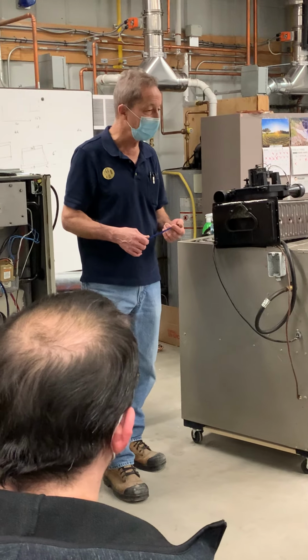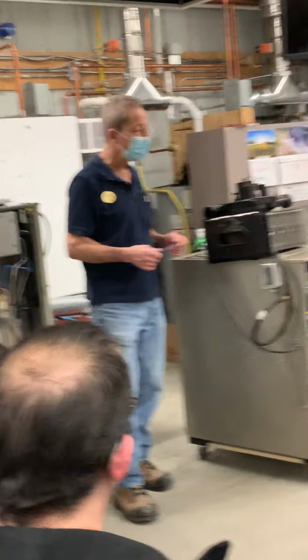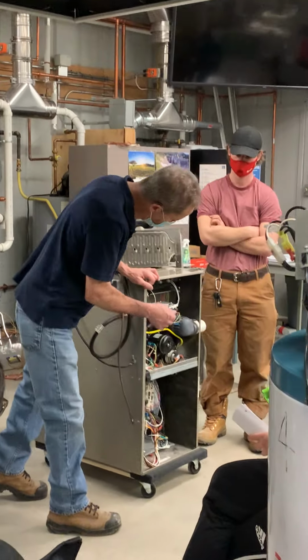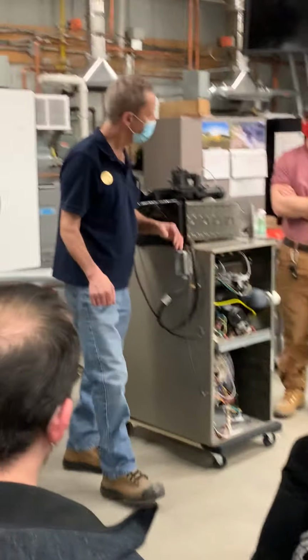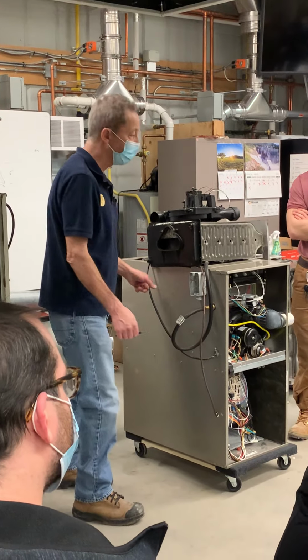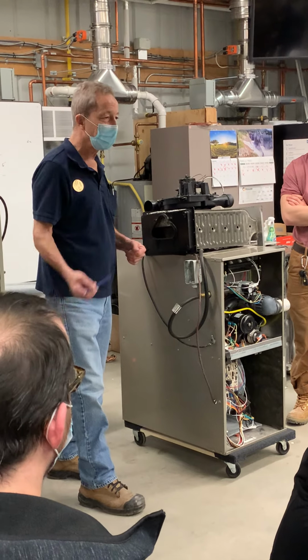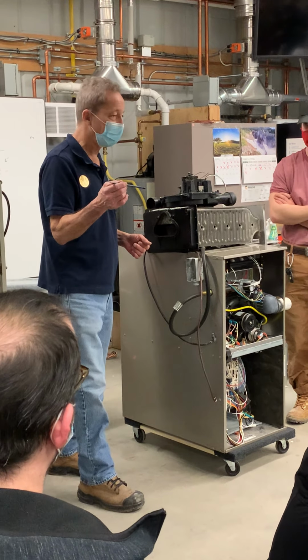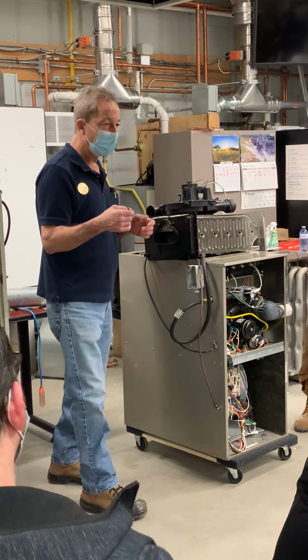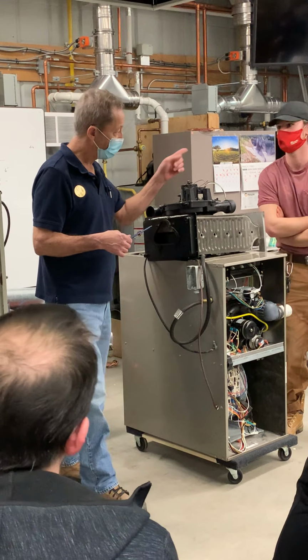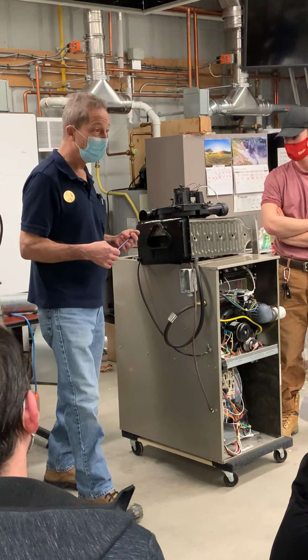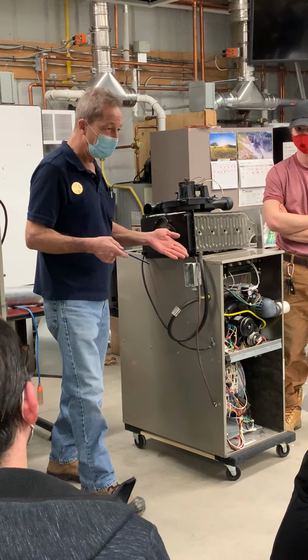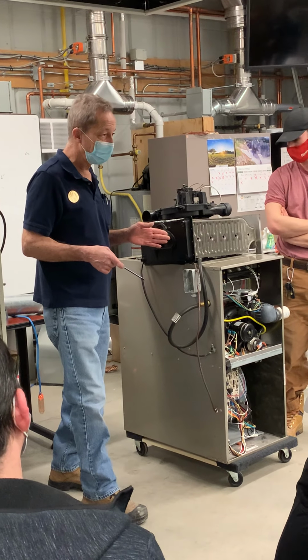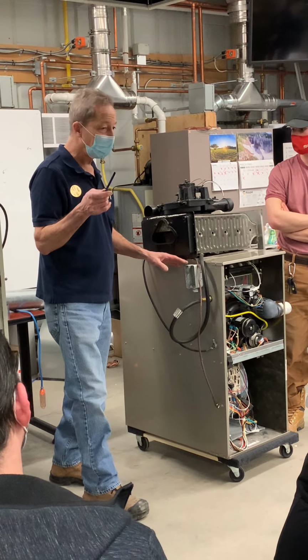The flame comes on. The problem is, the flame is not being sucked into the burner area. It's not being sucked through the primary and then through the secondary because it's a blocked secondary heat exchanger. So what do you think happens? Rollout. Flame rollout. Thank goodness we got a flame rollout. So if you come to this appliance, it's a flame rollout trip. Think about a blocked secondary heat exchanger.